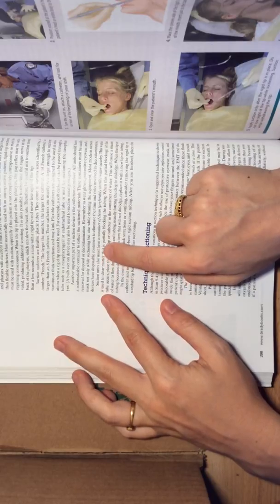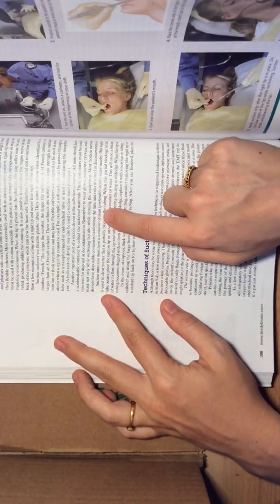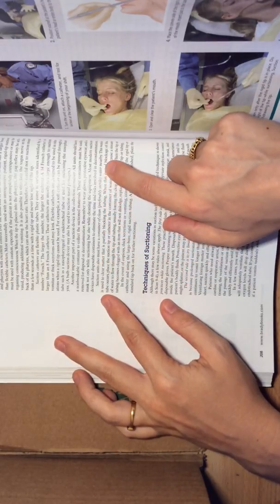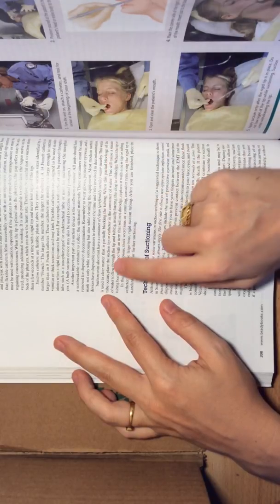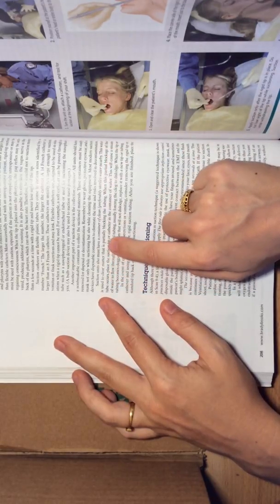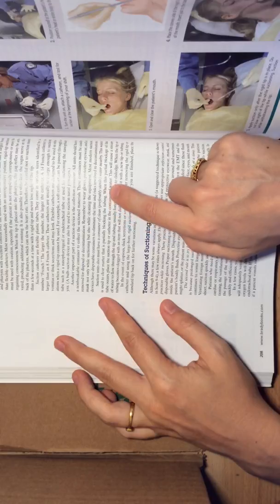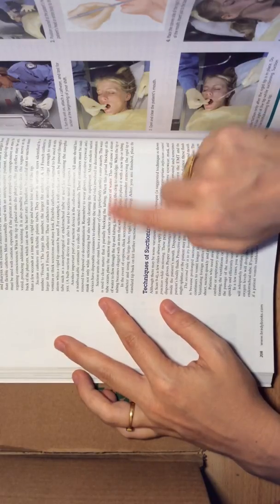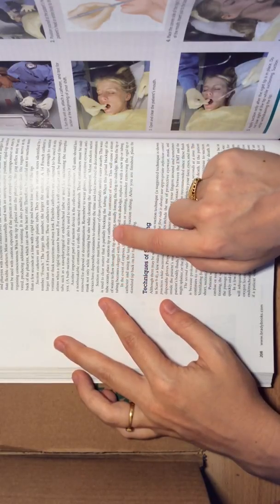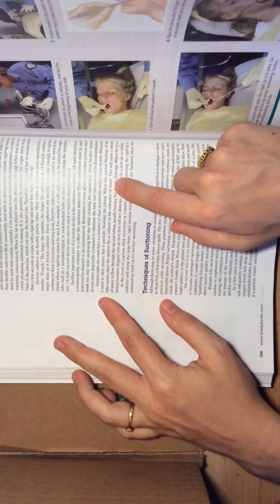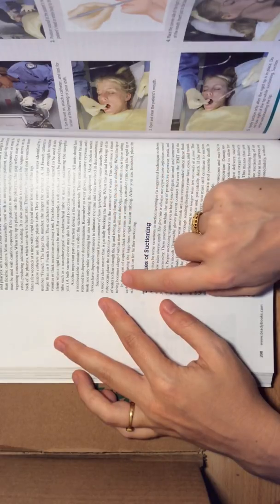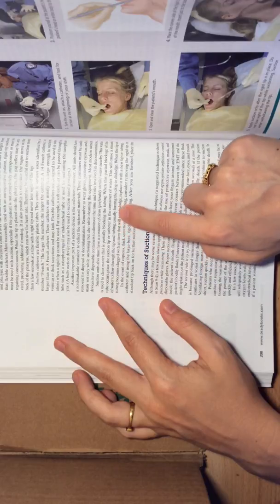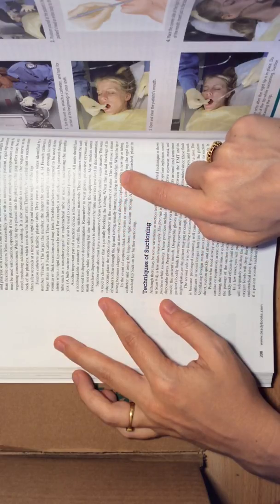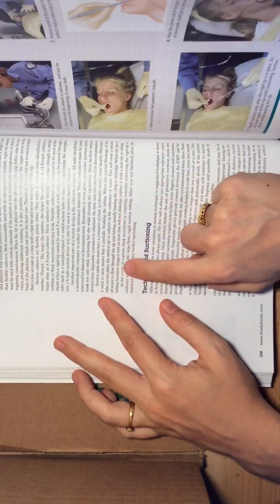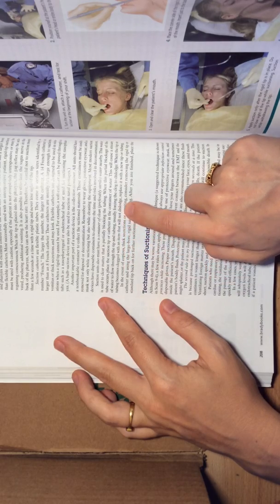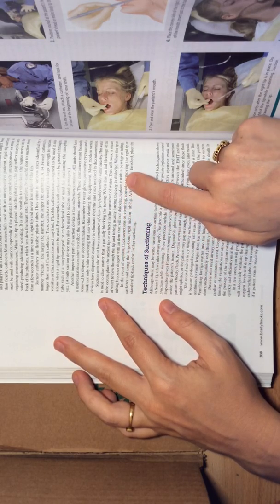Suction units also must have a container of clean, preferably sterile water nearby. This water is used to clear matter that is partially blocking the tube. When this partial blockage of the tube occurs, place the suction tip or catheter in the container of water. This will cause a stream of water to flow through the tip and tubing, usually forcing the clog to dislodge.